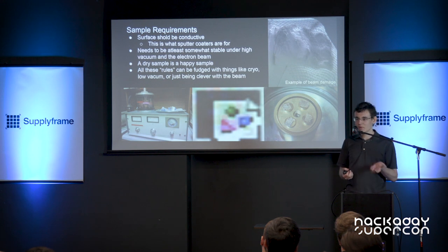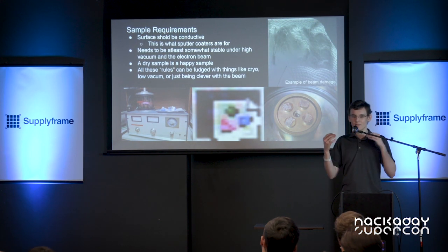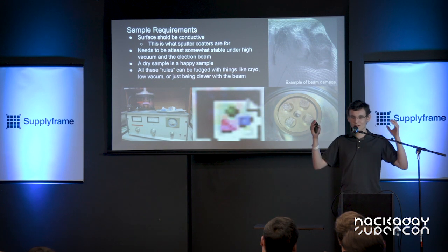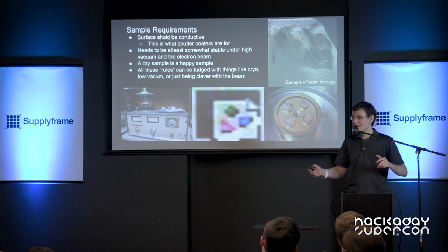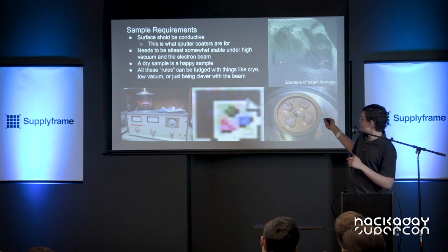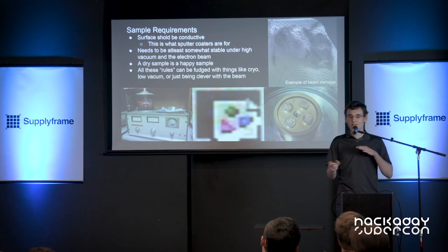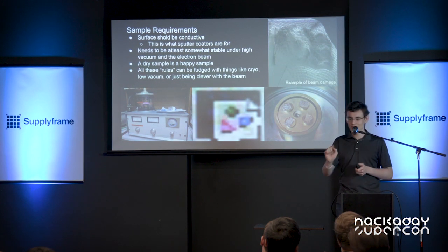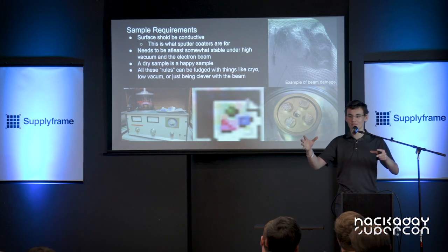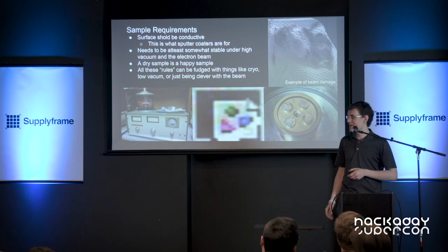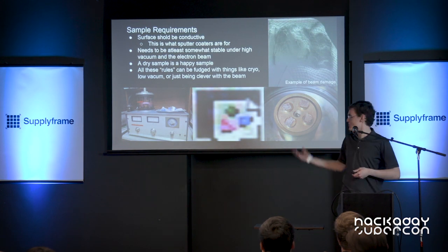The samples also need to be stable under high vacuum and the electron beam. The electron beam is, in some ways, the radiation of a nuclear blast concentrated down to a couple of nanometers hitting your sample — and the hope is not to damage anything. Good luck. This is what happens when you get too powerful of an electron beam — that's the eye of a fly. There was a slight miscalibration in the instrument, so I pressed a button to try to make the image brighter, and then the surface started boiling off because the beam was literally melting it.